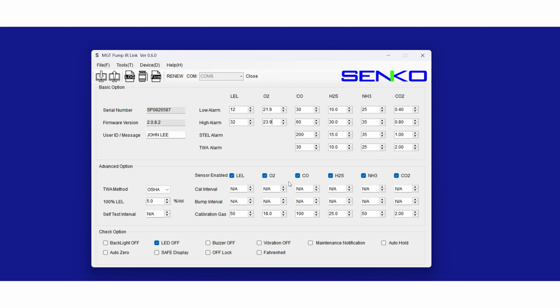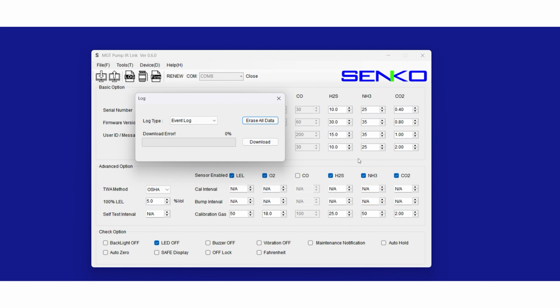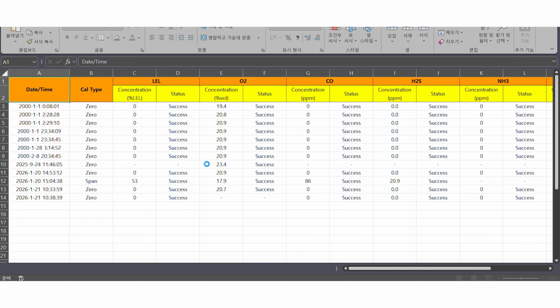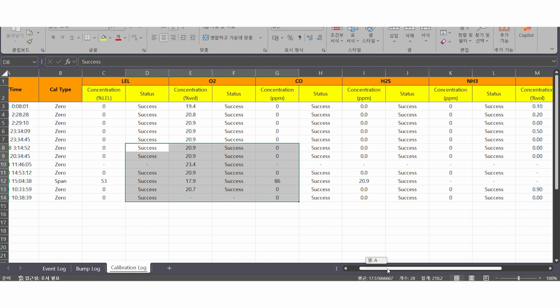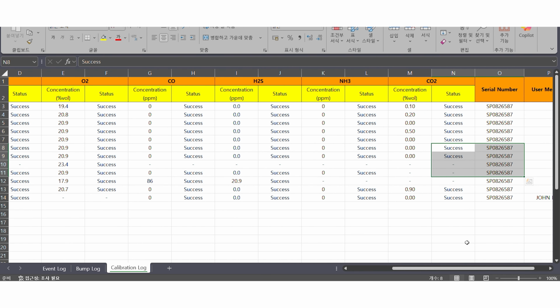In the Alarm Settings menu, you can set the low, high, STEL, and TWA alarm values for each gas. In the Calibration menu, zero and span calibration can be performed more easily. The Interval Settings menu allows you to set the calibration interval and bump interval, helping you manage regular inspection schedules in a systematic way. In the Check Option menu, you can configure device operation options such as the LED, buzzer, and vibration. Finally, in the Log menu, you can download measurement data, alarm events, calibration records, and bump test history to your PC for reporting and record management. In this way, the IRLINK provides a simple and efficient PC-based solution for configuring, calibrating, and managing the SP-MGTP.